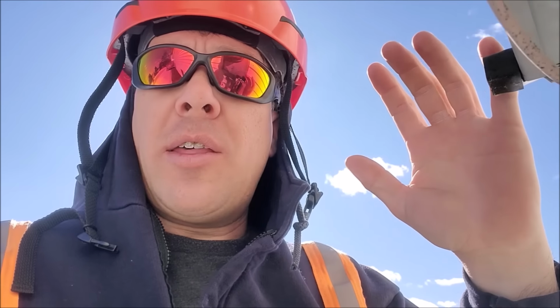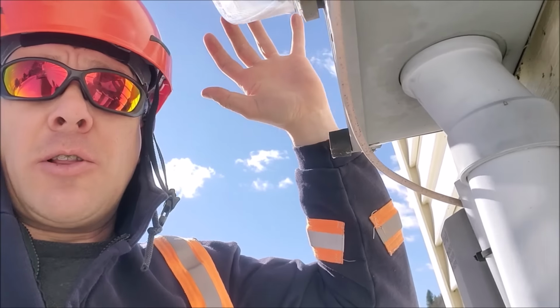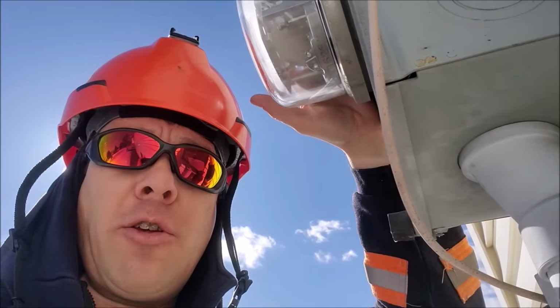So here we are at their meter right now. The only way that a bad neutral is gonna show up on our readings is if there's a load on the meter. Once we pull that meter, there'll be no load, and the voltage should revert back to normal. We're gonna use a meter puller here.